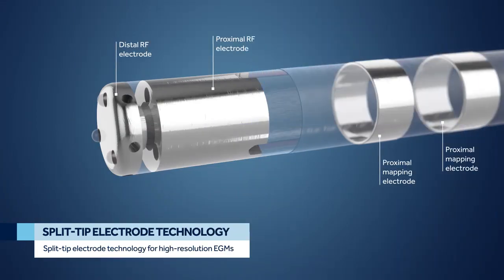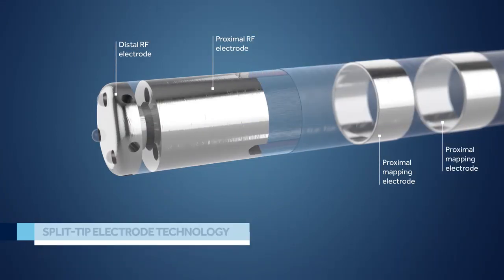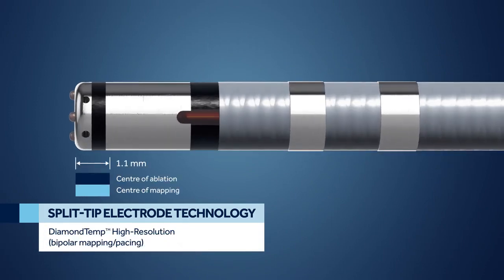The 1.1 millimeter catheter tip segment consists of a split-tip electrode, which is electrically isolated, allowing for clear, high-resolution EGMs at the ablation location.